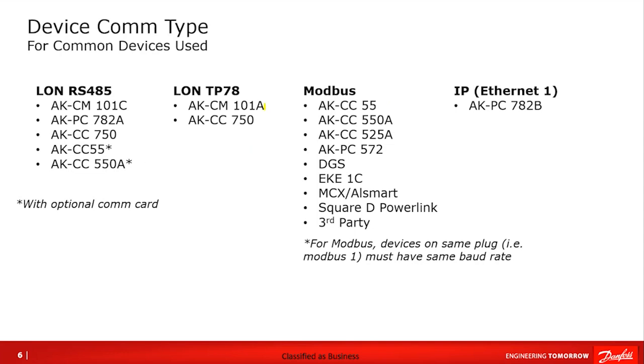For Echelon TP78, another format of the COM module — the CM 101A — so we always want to pay attention to what COM module we're using and make sure it matches the System Manager Echelon type. That's our breakdown between a 101C and 101A. We had another version of the 750 listed under both categories — two separate part numbers, one for a 485 communication style and one for TP78.